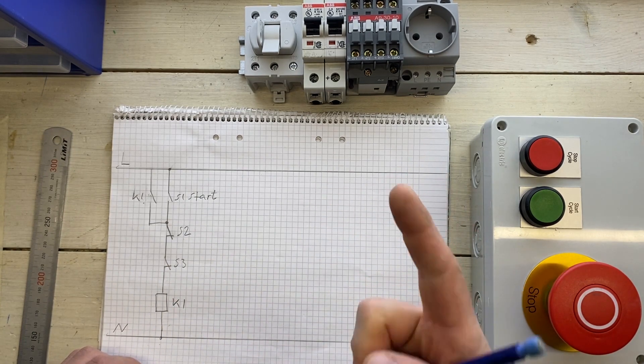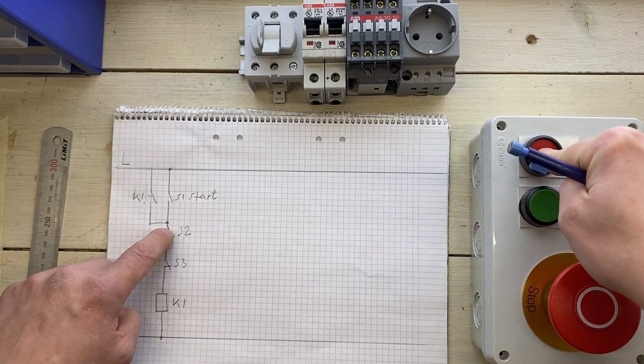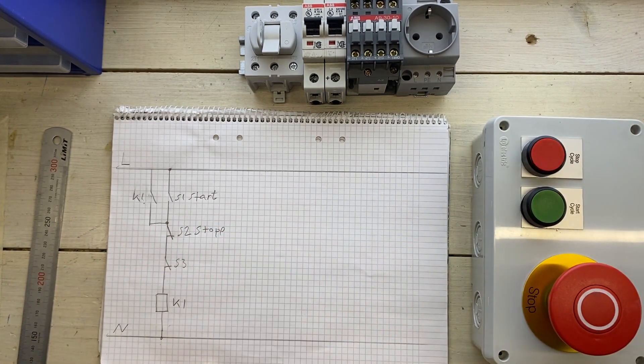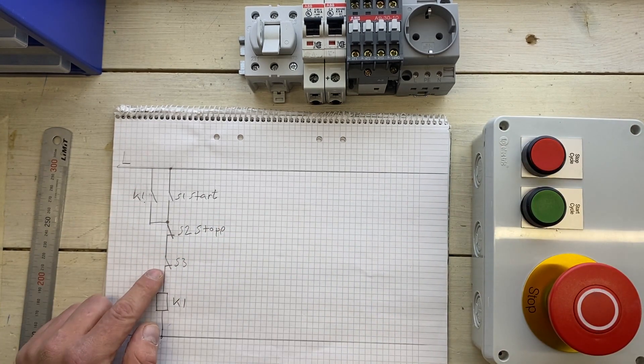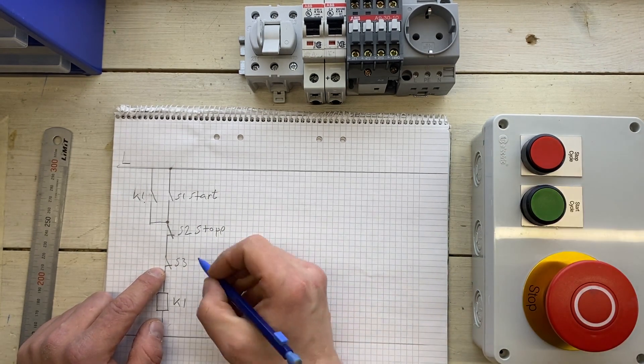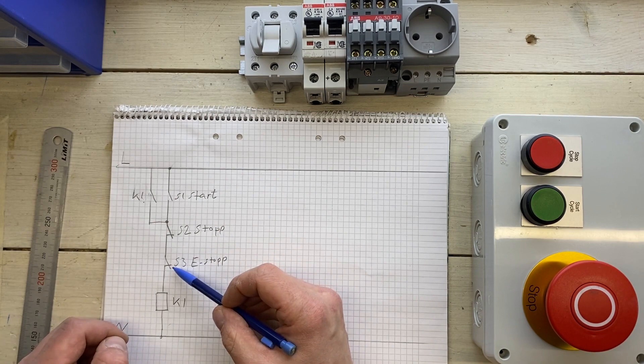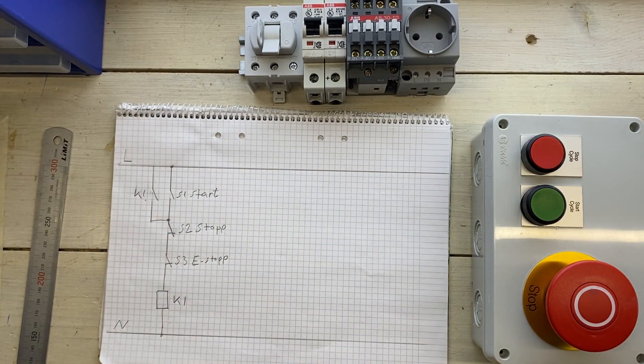So how do we get the relay coil to release? Well, we have two ways to do this. One, push the stop button, S2 opens, and K1 releases. Or push the emergency stop button. And in that case of course, S3 opens, K1 releases, and the contactor is reset. And this is what I'm going to hook up here to show you.